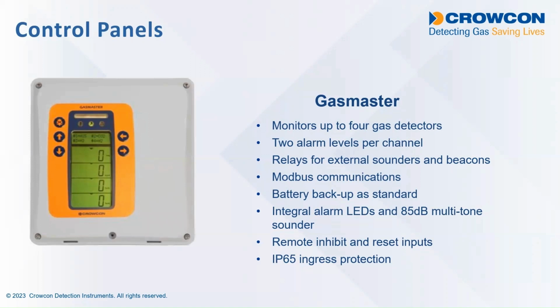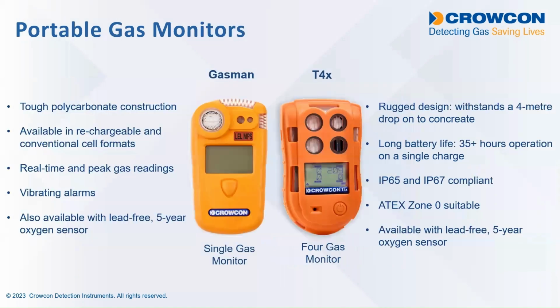It has a loud sounder and a very bright beacon built into it, so if gas is detected above an alarm threshold, then the user is alerted very clearly. And of course you can see the gas concentrations on the display of up to 4 gas detectors. And then it has relays in there for triggering loud sounders and beacons, Modbus communications for sending information to other plant-wide building management systems or DCS systems. And being a safe system, it has battery backup as standard, so if the mains fails, the system keeps working seamlessly. And it has a high ingress protection, IP65, so if there is washdown operations or water being sprayed around, then it has a good level of protection against water ingress.